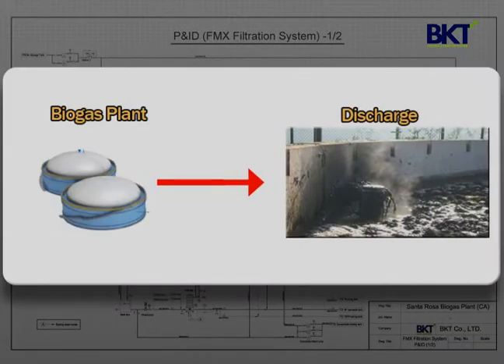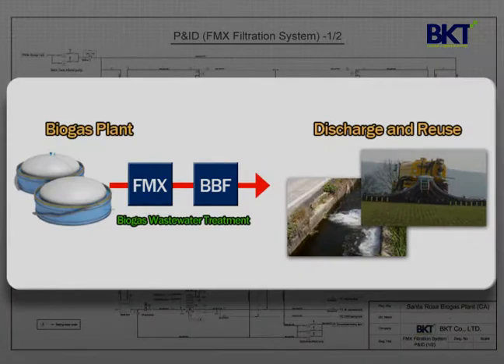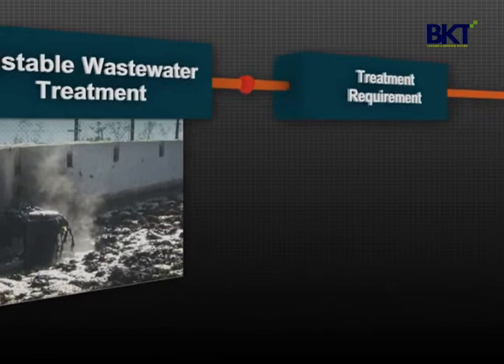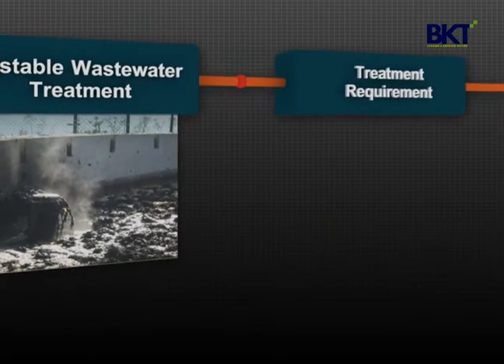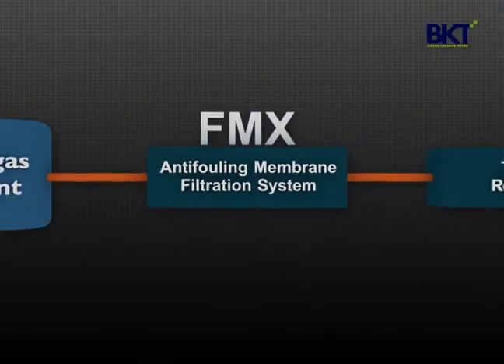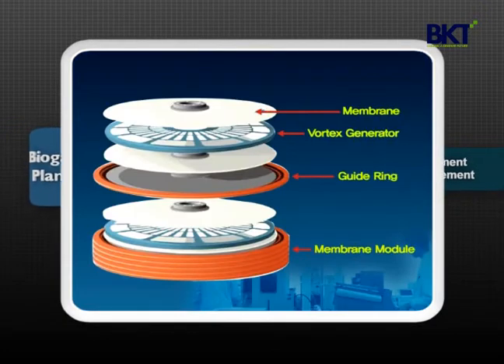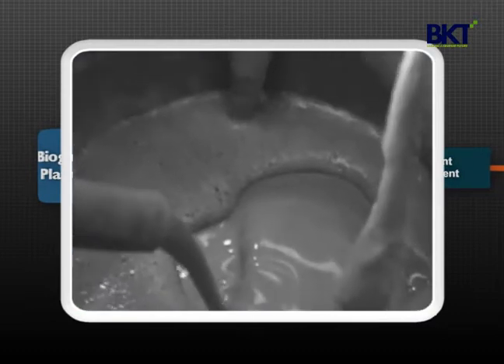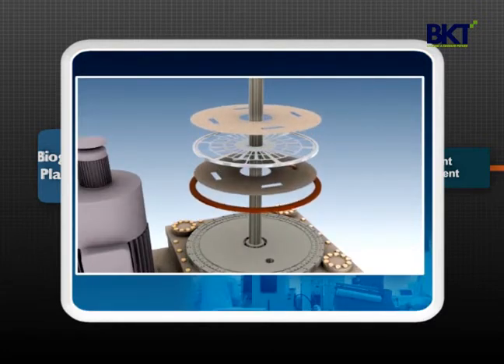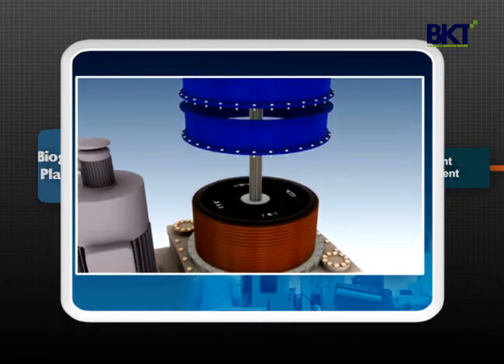Biogas plant wastewater management is not a minor issue, but a main issue that needs to be addressed properly from an early planning and design stage. Unstable wastewater treatment could be a bottleneck for successful implementation of biogas plants. BKT's anti-fouling membrane filtration system, called FMX, is a proven performer that treats anaerobic digestate without succumbing to fouling problems common for conventional membrane systems. Rotating blades between the membrane surfaces of FMX generate what are known as Karman vortices and maintain turbulent conditions on the membrane surfaces to minimize membrane-fouling propensity.